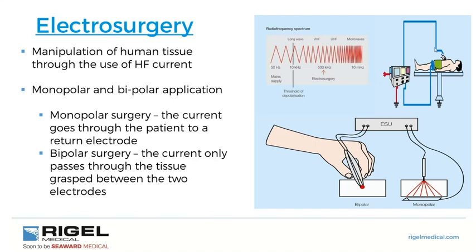Looking at the diagram, we have the patient on the table and the return plate fed back into the ESU. The bovie pencil is the active electrode, which has high current density produced by the tip of the probe for localised thermal heating — this is where all the destructive effect occurs. The return plate has a larger surface area and produces a thermal effect but not a destructive one. This results in thermal heating used for cutting, fulguration, and desiccation of tissue.